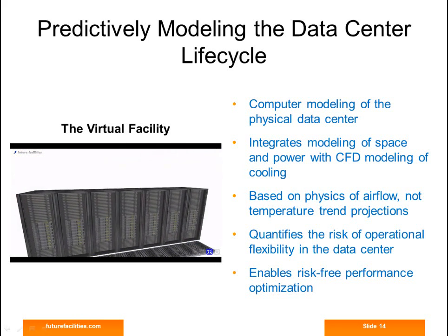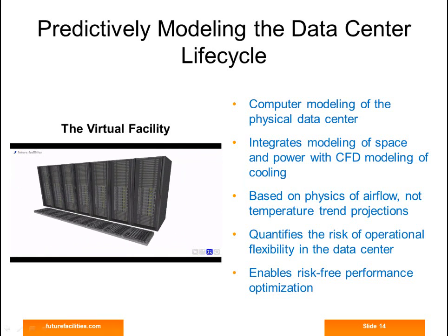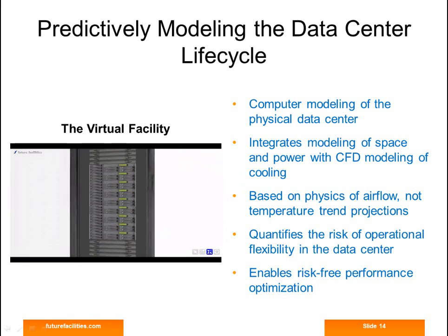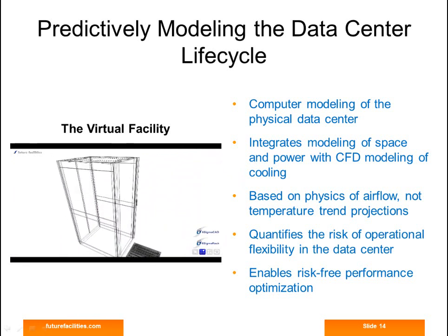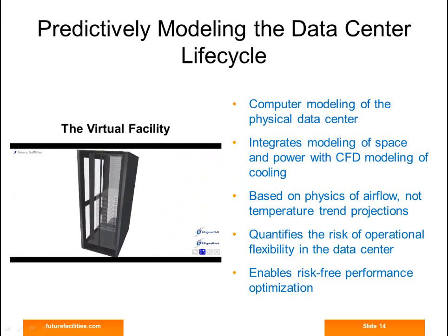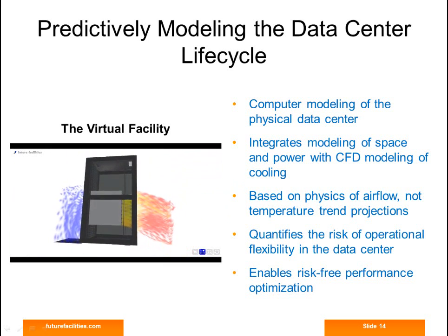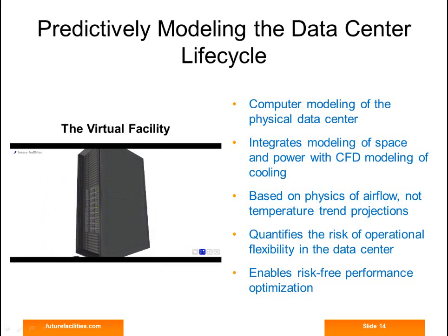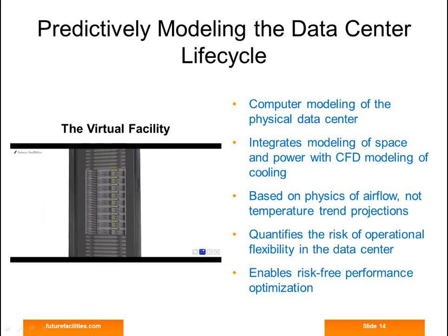This granular CFD modeling approach overcomes the problem of having to use non-physical and misleading modeling techniques, such as temperature trending. The virtual facility is used to quantify the costs and the risk of breaking the design assumptions, and this enables operational flexibility to the operator. It is also used to mitigate risk from operational flexibility at effectively no cost.